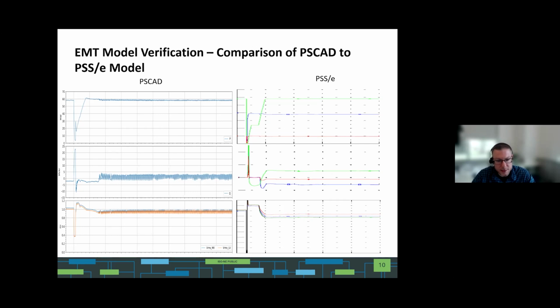This is getting to where there's control interactions and oscillations, high frequency oscillations, that you can see in EMT space, which can happen on the real system, but you would never see them if you were only running a positive sequence simulation.